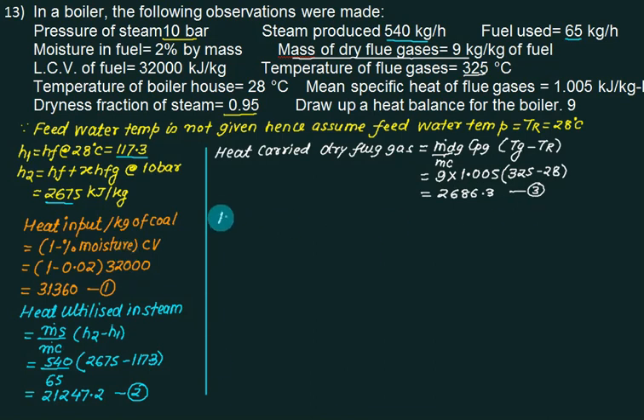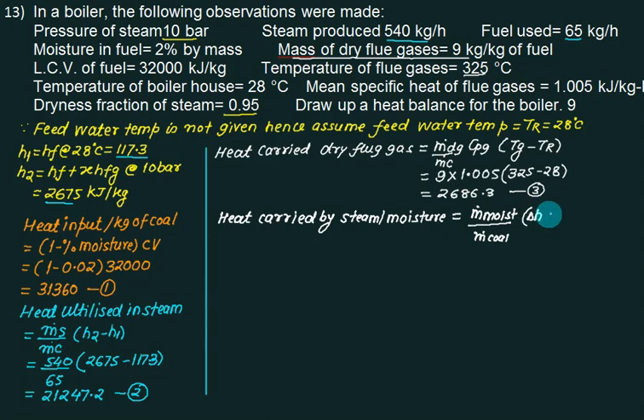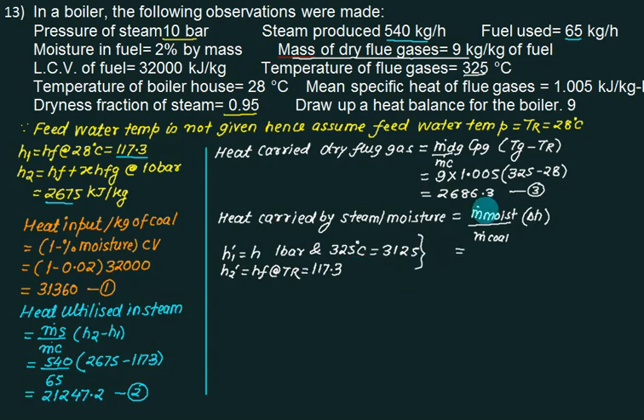Next, heat carried by moisture or by steam. This equals mass of moisture divided by mass of coal multiplied by delta H. Now how to calculate delta H? First you have to calculate H1 dash. What is the pressure and temperature of flue gas? Temperature is 325°C. See the steam table and find out H1 dash. Next is H2 dash, which is hf at room temperature, equal to 28°C, already known to us as 117.3. The mass of moisture per kg of coal is 2%, which is 0.02. This gives 3125 minus 117.3 for calculation number 4.